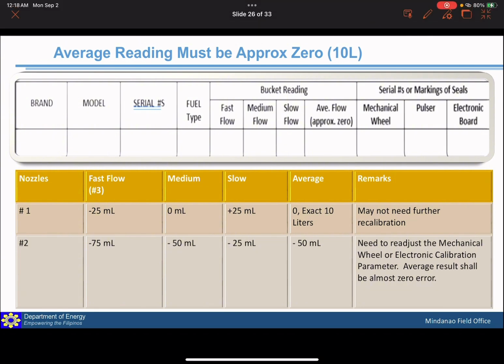Let's have an example. So for the first nozzle, the fast flow reading is minus 25 ml. Then medium is 0 ml. Then slow, plus 25 ml. Average of 0, which means it is exact 10 liters. Then the remarks: may not need further recalibration. For number 2, second nozzle, the fast flow is minus 75 ml, the medium is minus 50 ml, and the slow is minus 25 ml. The average is minus 50 ml. So the remarks is need to readjust the mechanical wheel or electronic calibration parameters.